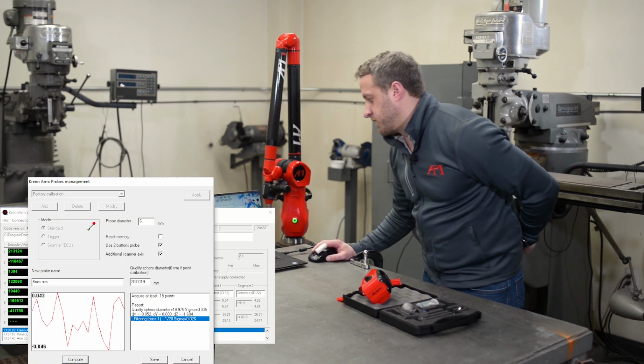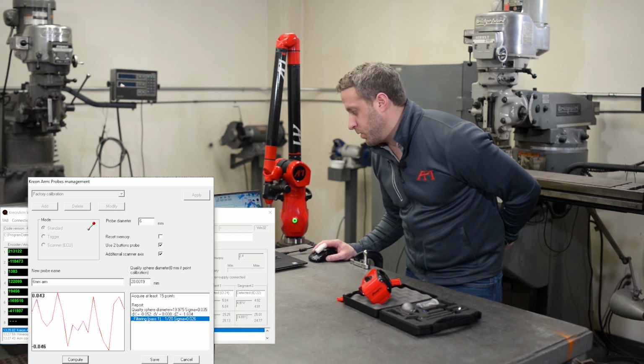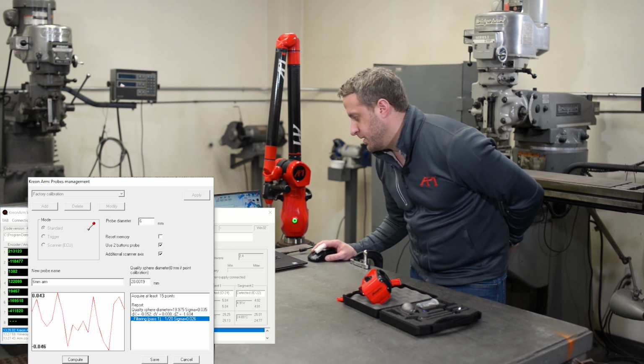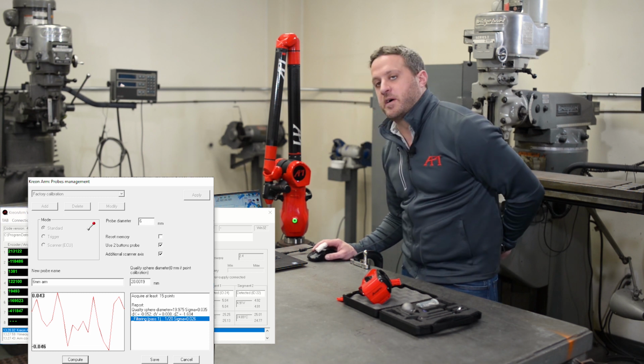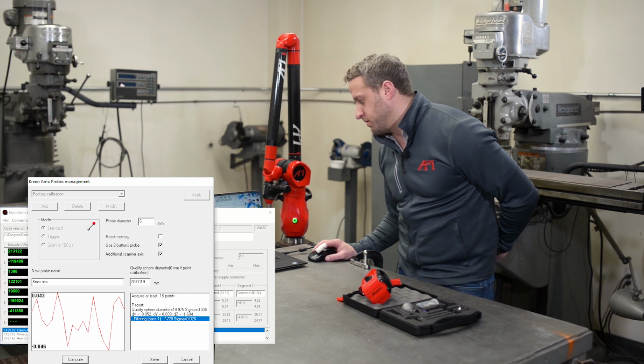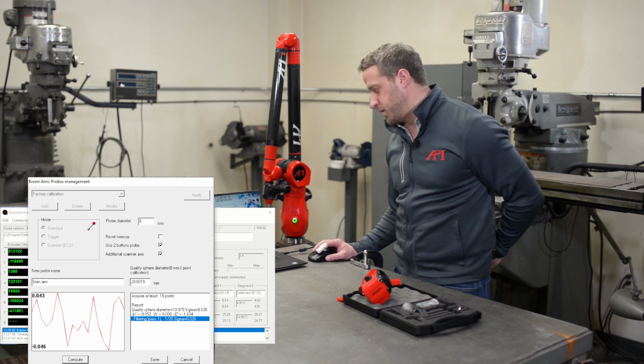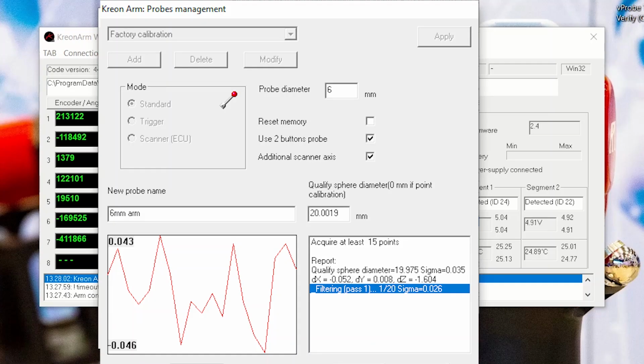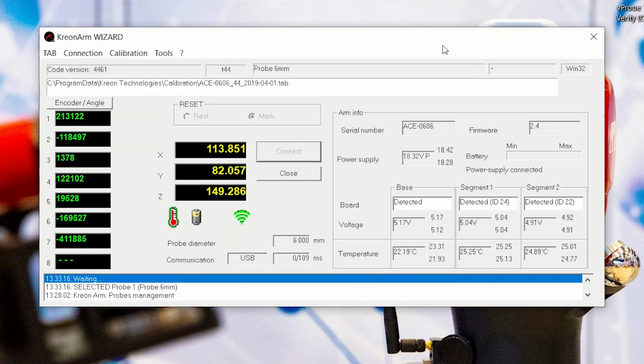This screen will give us an upper and lower point graph. It'll also tell us the sphere diameter that it had calculated, and it'll give us a sigma rating or the deviation from the nominal sphere diameter. So we're at 26 microns. That's within the 27 micron calibration standard. So we're gonna hit save and apply.